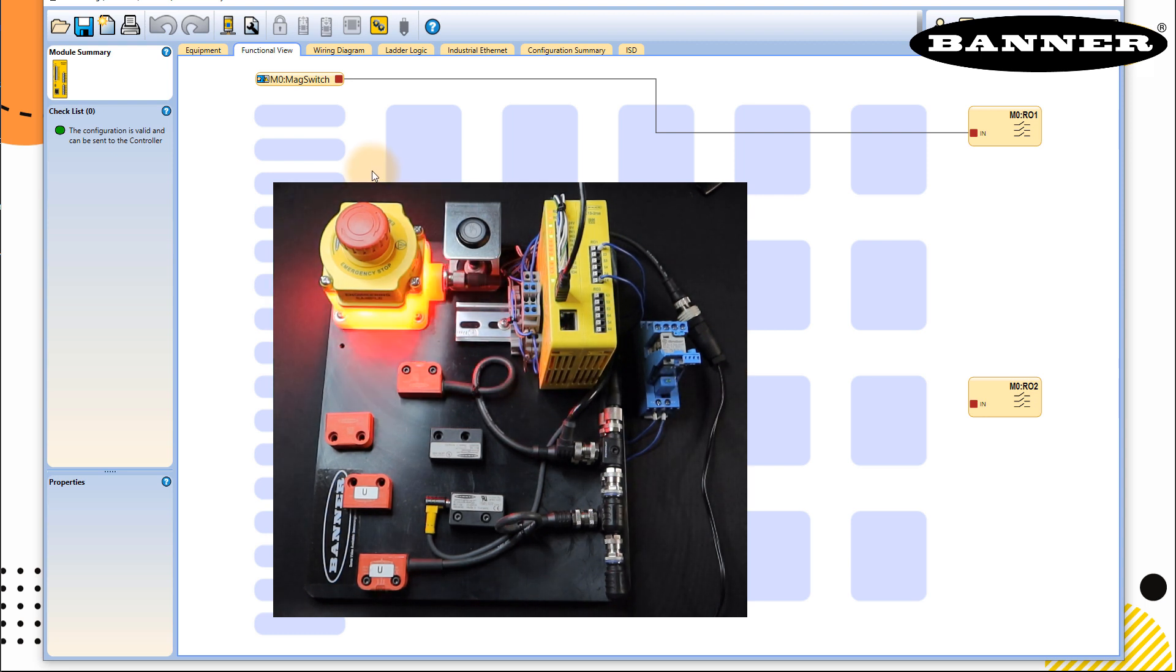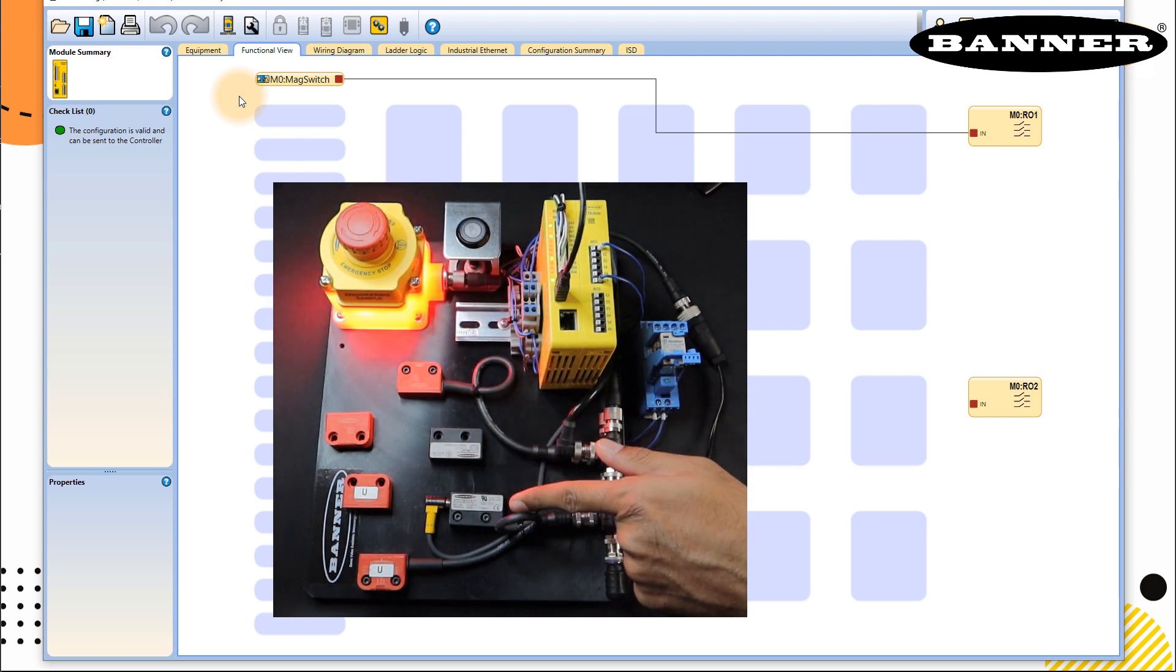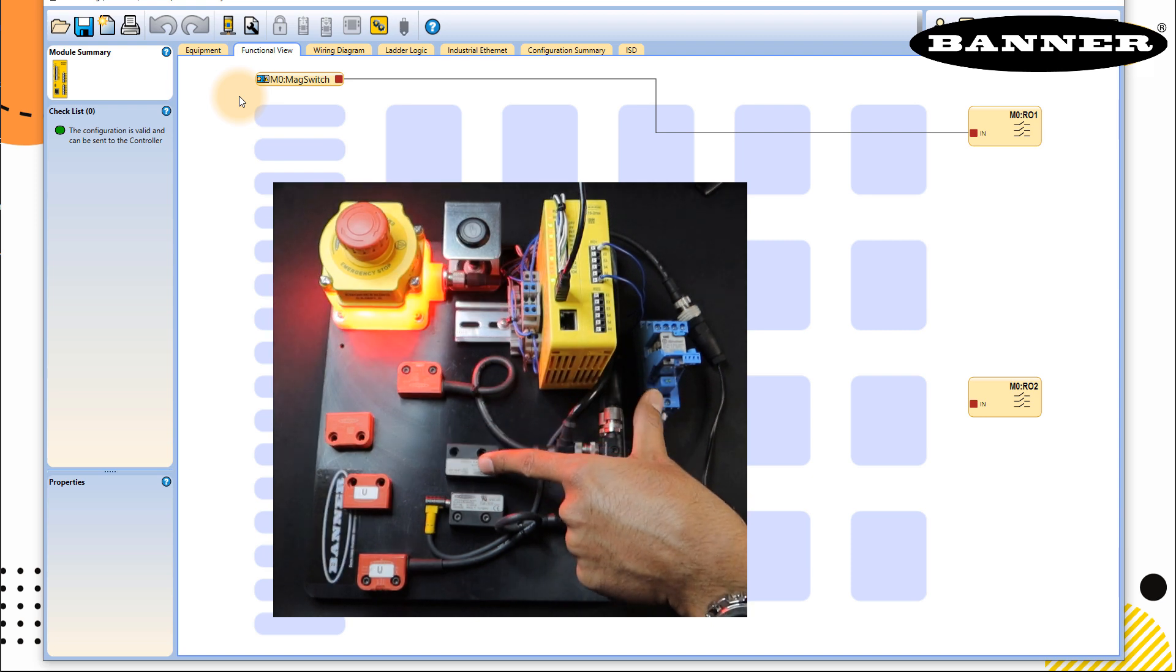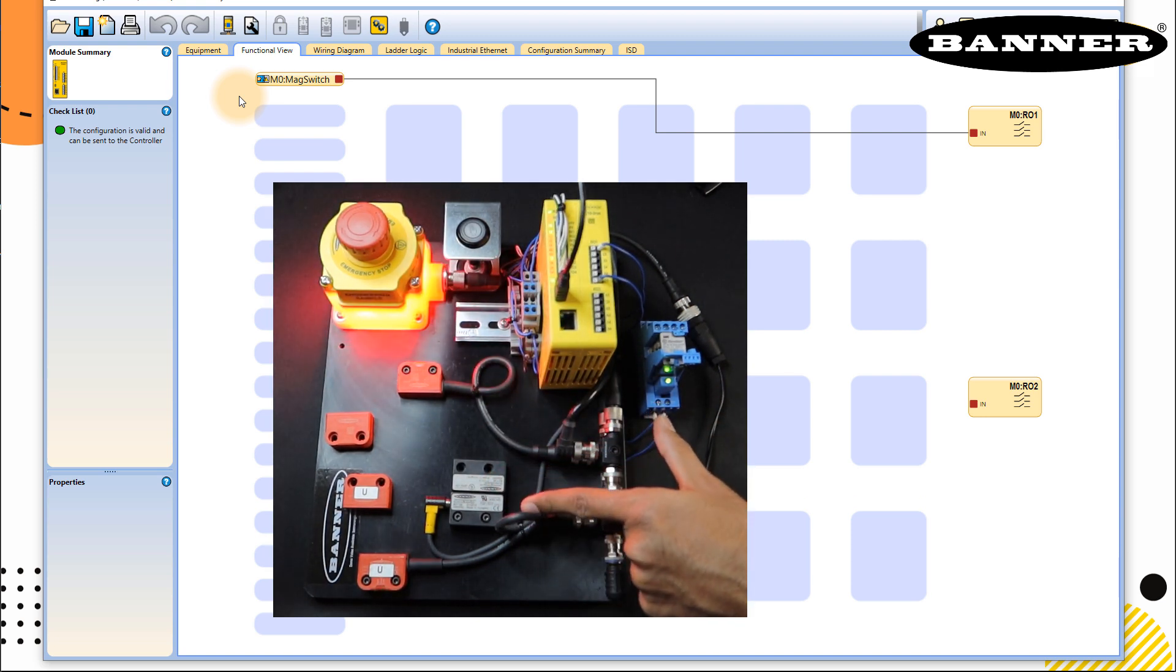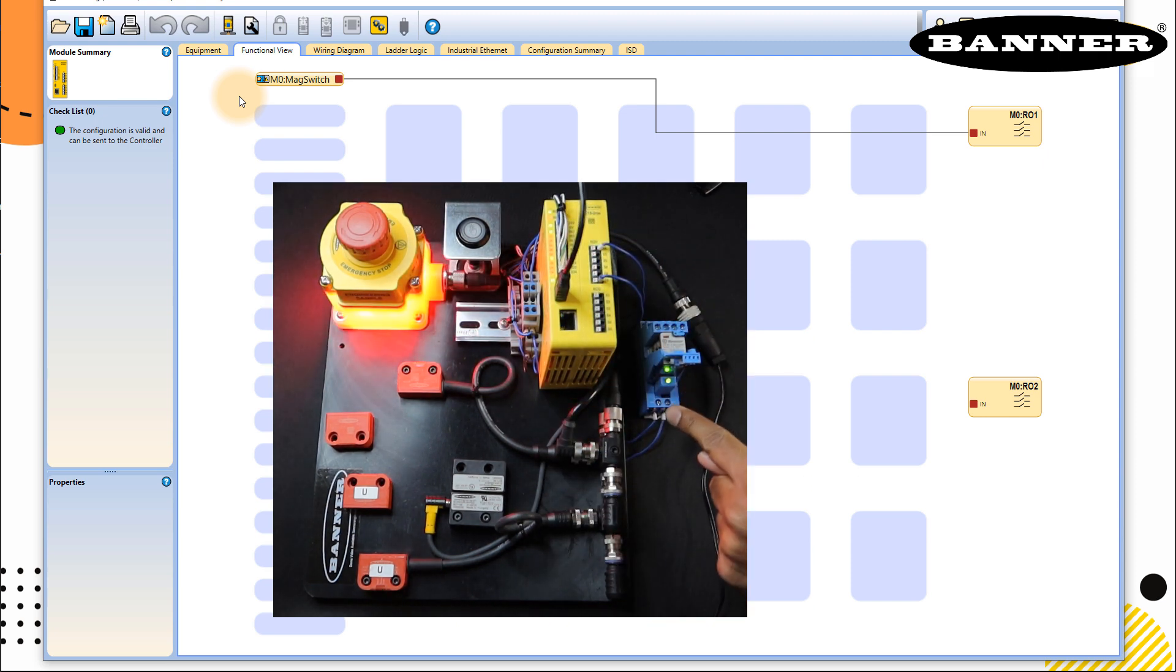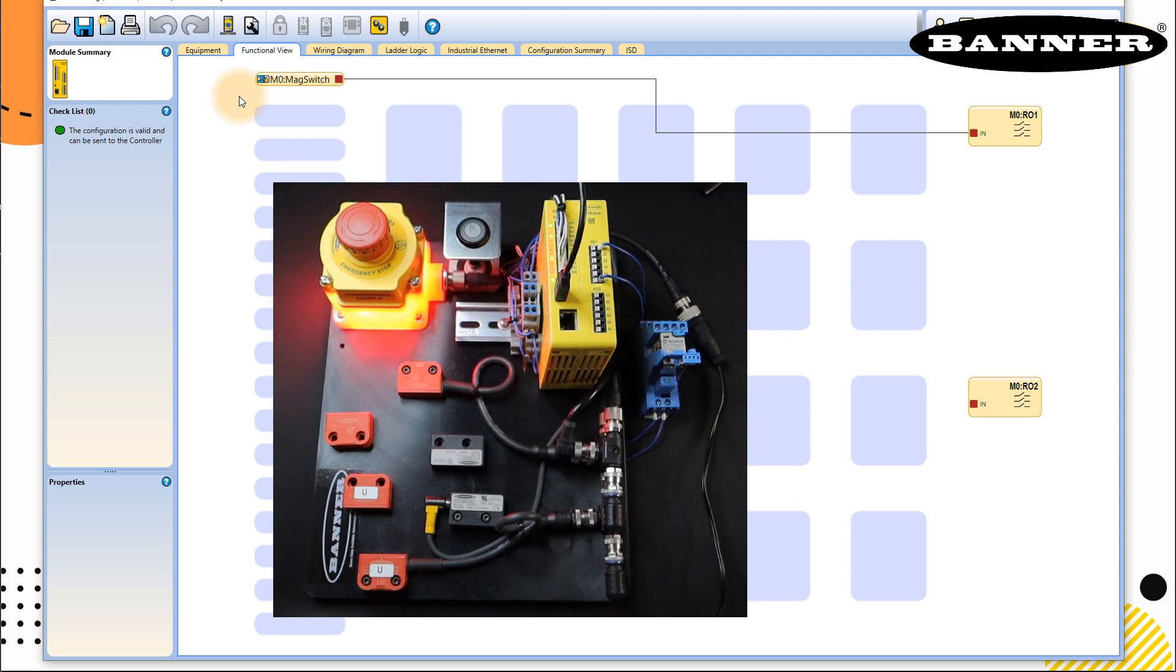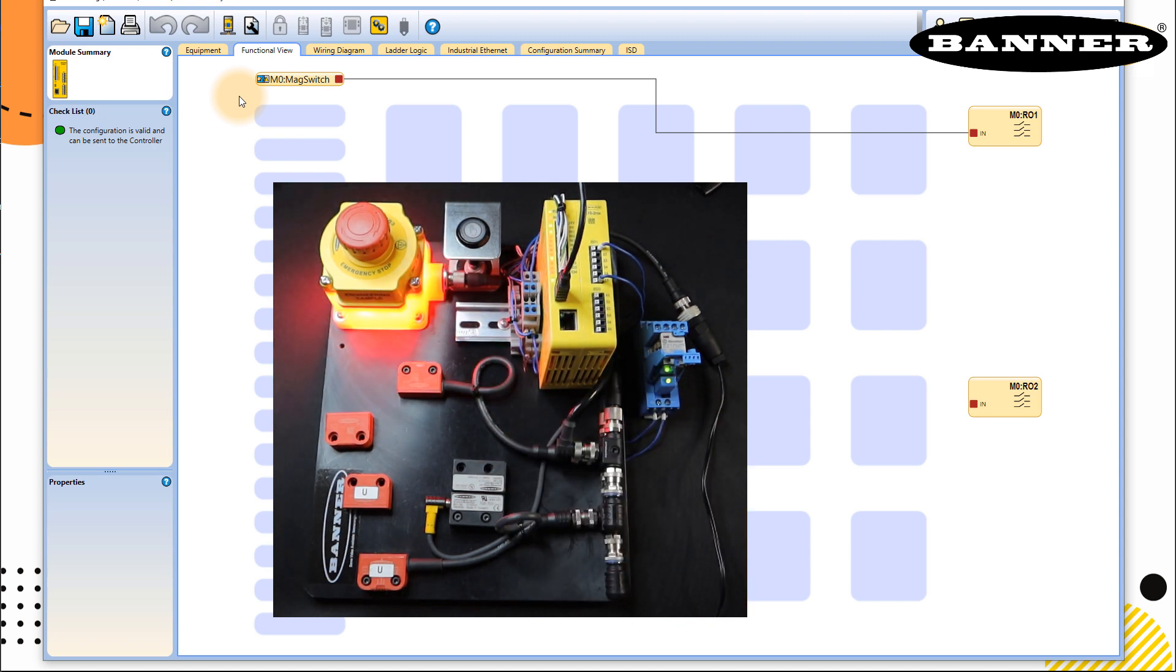Now everything looks fine. In our case, so let's check it out. How does it work? So I have to bring my contact towards this and to see if the output gets on or not. So now you can see that once this contact is closed with this gate switch, your output RO1 is true, which makes the relay true as well. So here you can see that again. Now it's off. And it's on again.